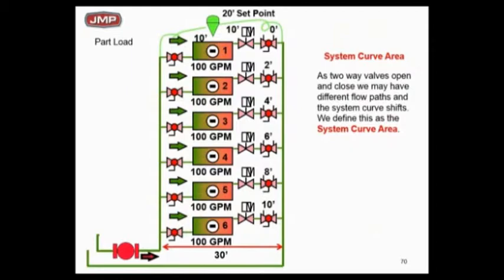compared to zone one. Go to zone one, take 100 GPM, and all the other zones are closed. You see it's the furthest one away. It's direct return. It's going to take more pump head to pump the same flow rate of 100 GPM through zone one than it does to pump it through zone six.